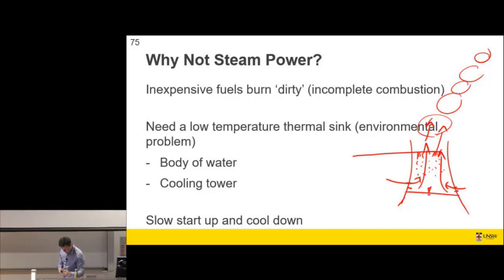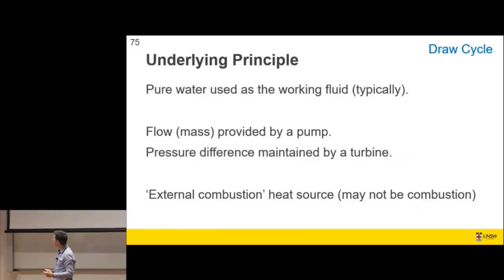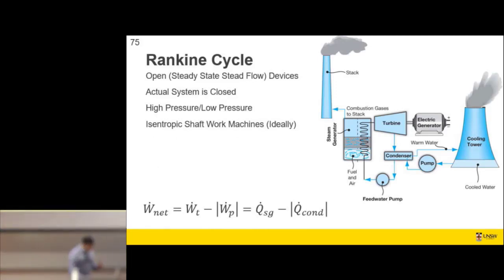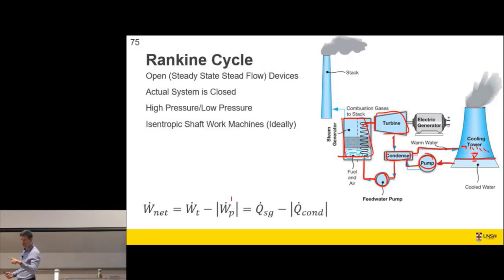The water that you're doing this with isn't the same water that you're passing through your cycle. So here's a diagram from Reissel showing, you can see you've got your boiler here, your turbine, your condenser, and your pump. That's a closed cycle. And then you've got an alternate cycle off to the right-hand side with a pump passing into the condenser, which is now a heat exchanger. So we can analyze heat exchangers, we know how to do that. It passes water that then the warm water comes out, gets sprayed into the cooling tower. Here's the lake of water at the bottom of the cooling tower, which is then pumped out.